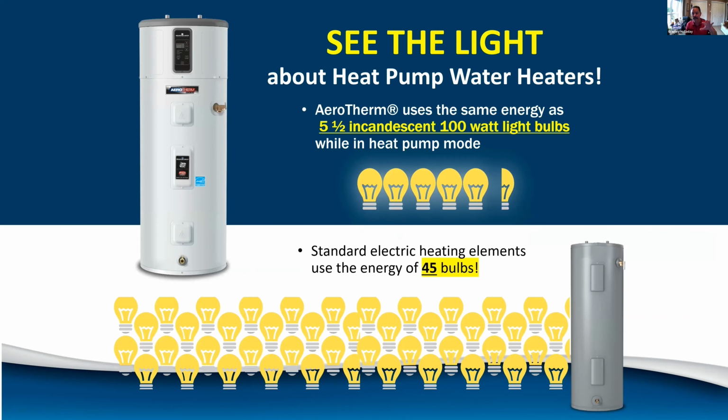Now, put this in perspective. When a heat pump water heater is running, it's about the equivalent of 550 watts of power. That's 5.5 100-watt light bulbs. That's it. 5.5 100-watt light bulbs. When standard electric heating elements come on, they're 4,500 watts. That's 45 100-watt light bulbs. That's the difference in using the heat pump to move heat versus resistance heat to create heat.